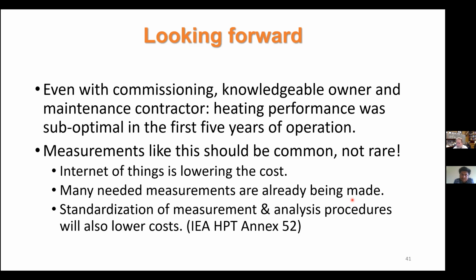The Internet of Things is lowering the cost all the time of making these sorts of measurements. A lot of the needed measurements are actually already being made. They may be internal to the heat pump. They may not be available to the owner of the heat pump, but they could be. Also, I think that standardization of the measurements and analysis procedures should lower costs. One of the reasons a study like this is so costly is because there's a lot of human effort after the fact to make up for the fact that we don't have all the sensors that we need. So if we planned ahead and had a better idea, we could lower the cost. And it's my own personal hope that this becomes much more common in the future. I, of course, also believe it'll show ground source heat pump systems are usually better than the alternatives, but whatever it shows, I'd like to know.